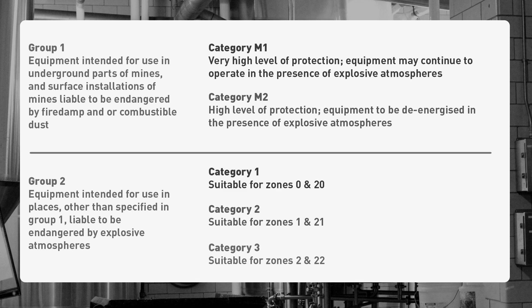Group 2 ATEX equipment is intended for use in any other ATEX rated environment other than specified in Group 1. Group 2 equipment is split into three categories: Category 1, suitable for zones 0 and 20; Category 2, suitable for zones 1 and 21; and Category 3, suitable for zones 2 and 22.